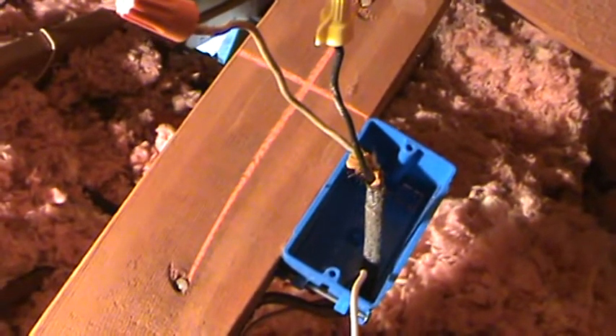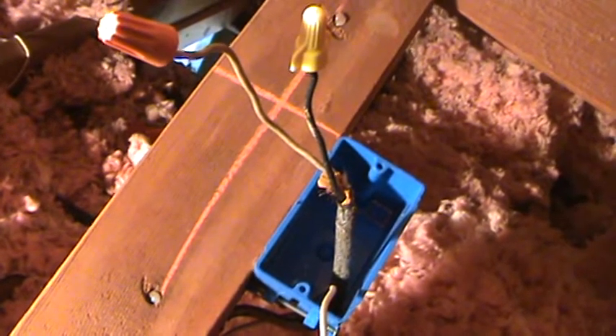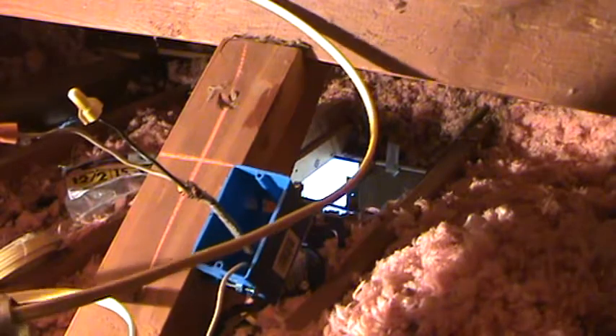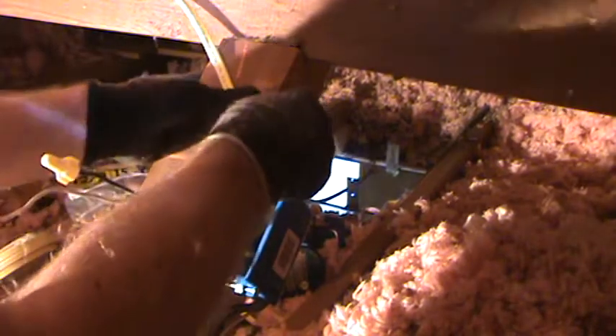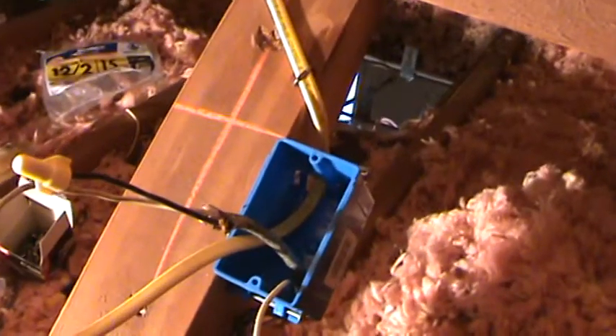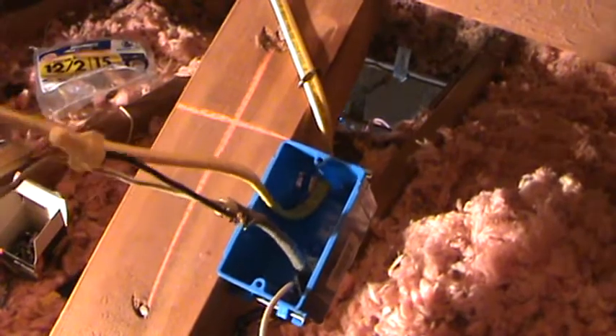That's our next step — that's for the switch and the lights. I've got to cut this and put it into there. I already got a knockout cut, so I'll shove the box in there like that. I've got to have six inches of wire inside the box to meet code. I've got it up there to keep it out of the way so I don't have to crawl over it, because you're not supposed to walk on these. Make it snug, not too tight.